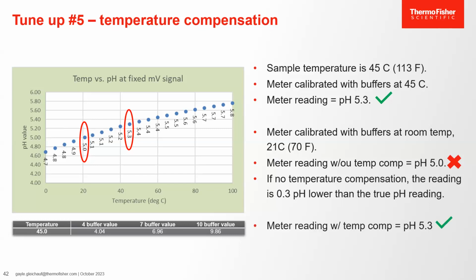Now my measurement will give me the correct pH reading of 5.3 pH units. With temperature compensation, I can calibrate at room temperature and get good pH results for samples that are at other temperatures.